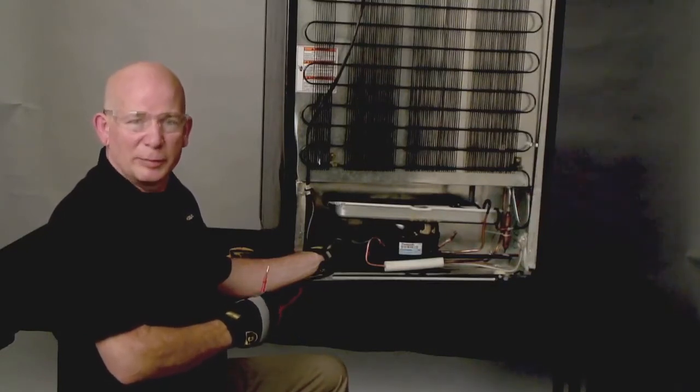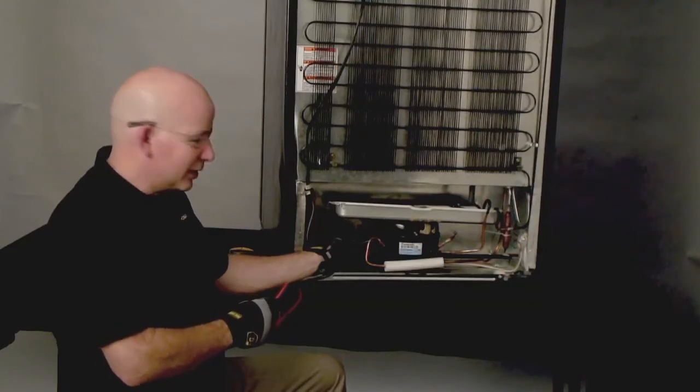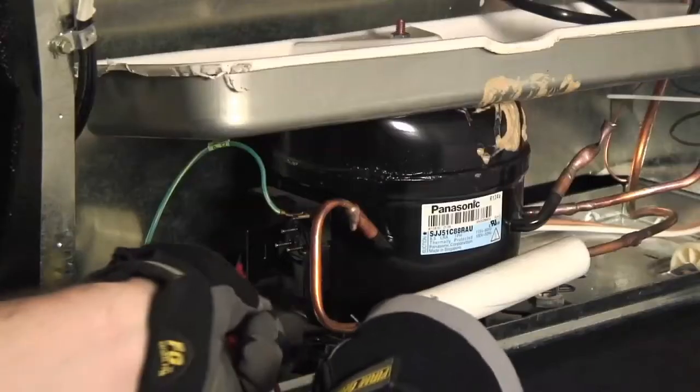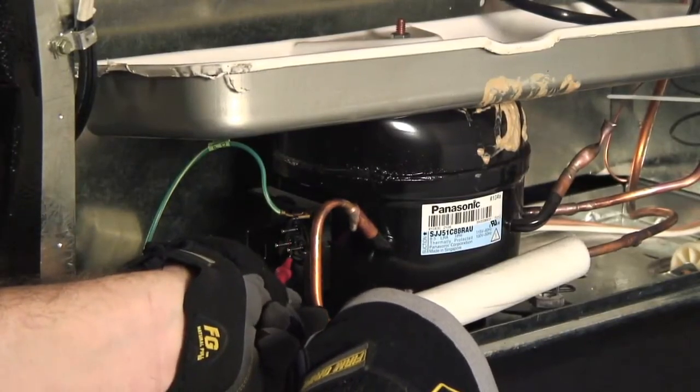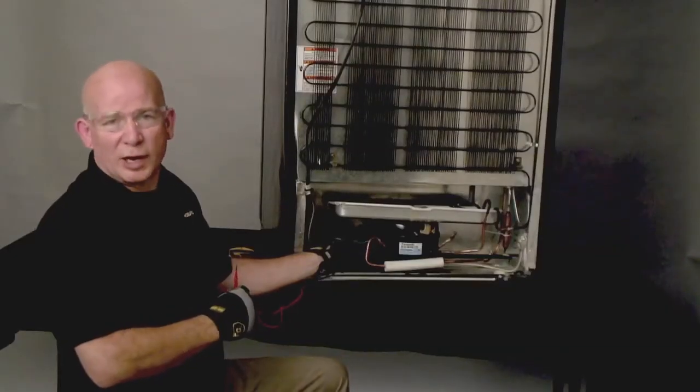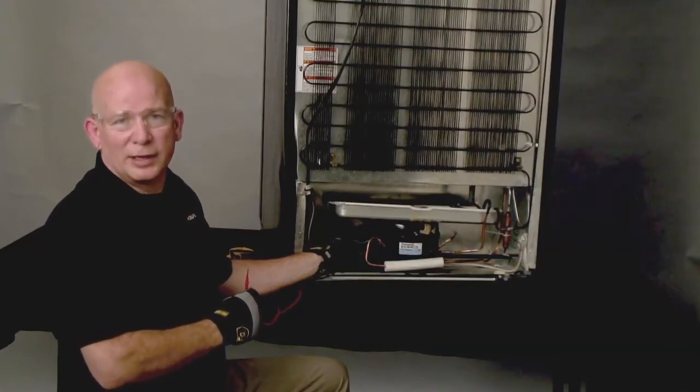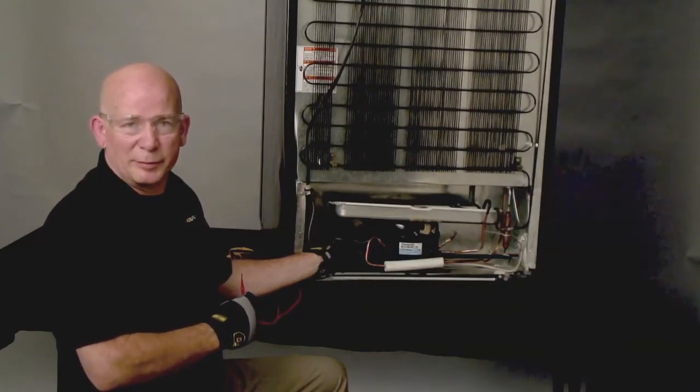If these readings are all similar, your compressor is shorted and needs to be replaced. Next, test each three terminals to ground. If any of these show continuity or are grounded, then your terminal is grounded and it is a bad compressor that needs to be replaced.